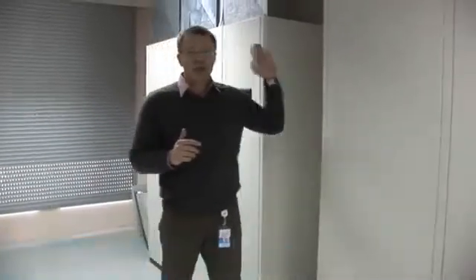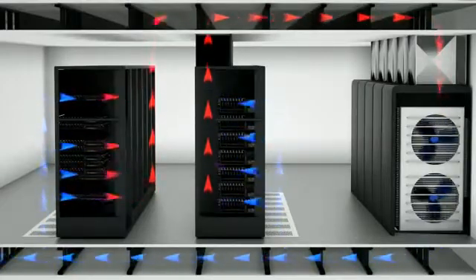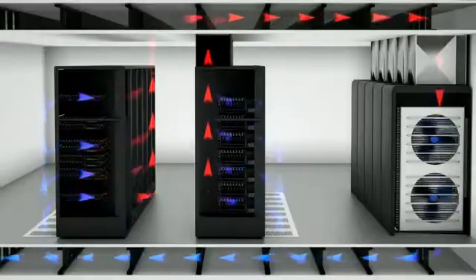This room is supported by four chillers which generate chilled water to support 10 air conditioning units in the room, in an N+1 configuration. They distribute cold air through a raised metal floor to the racks of servers, and the most critical parts of the whole cooling system are connected to the UPS. For cooling efficiency we have a hot and cold aisle design here.